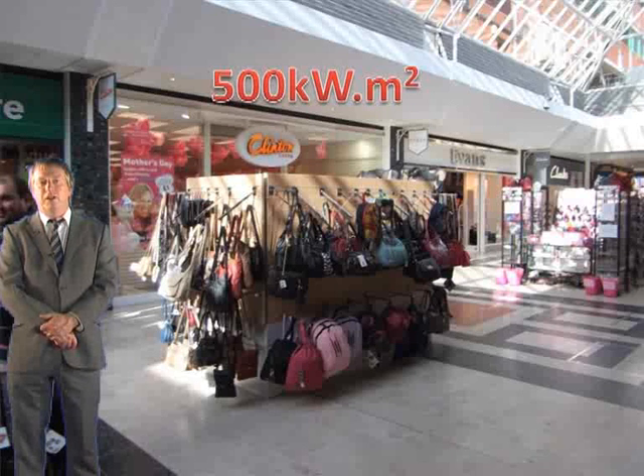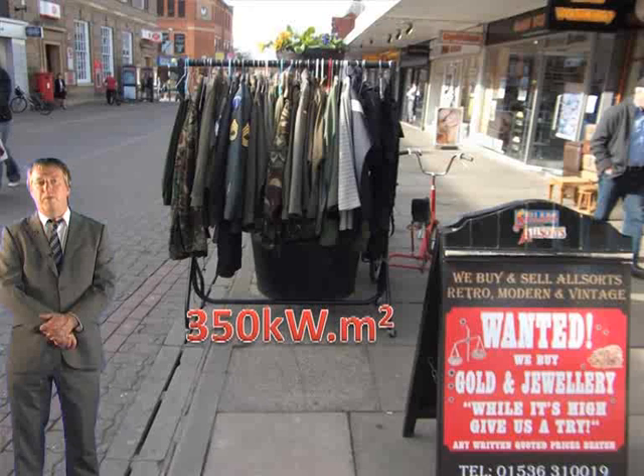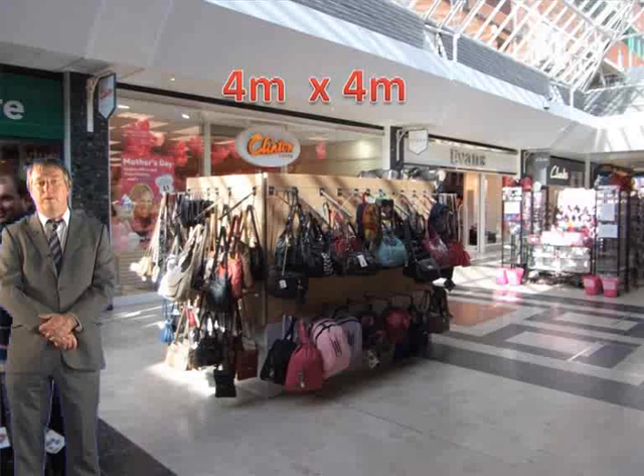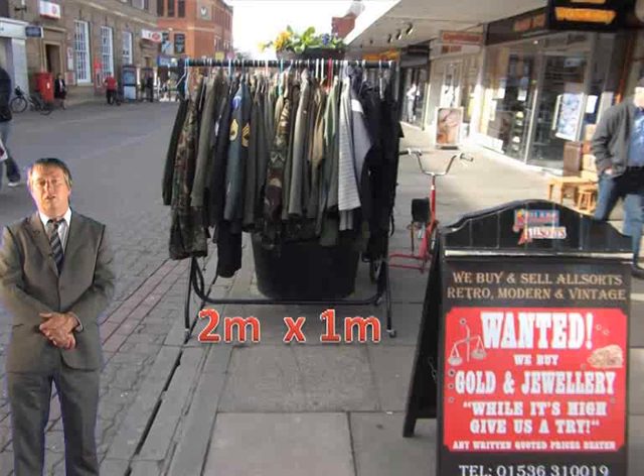Firstly, we need to know the heat release rate density of the material that may be on fire. That is the heat output per square metre. We also need to know how big the fire may reasonably be expected to grow to in terms of its physical size. And finally, we need to know the proportion of the total heat output that will go into the plume as convective heat. The heat release rate densities for various items can be obtained from databases held by the BRE or the NFPA or from other organisations that do research in this field.